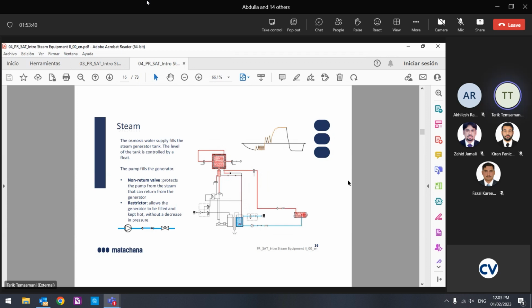What is the role of the restrictor in the circuit? The pump gives water here, and we have to control the flow, not put it at maximum. So with the restrictor we control the pressure and flow. This restrictor has a small diameter inside, which means sometimes it does not give water, and we have to clean or replace it. Also the one-way valve. So the circuit is clear.